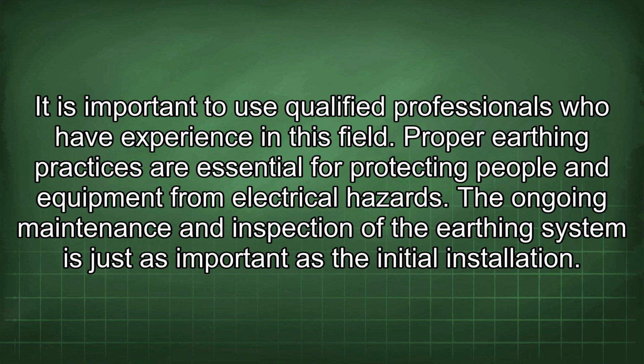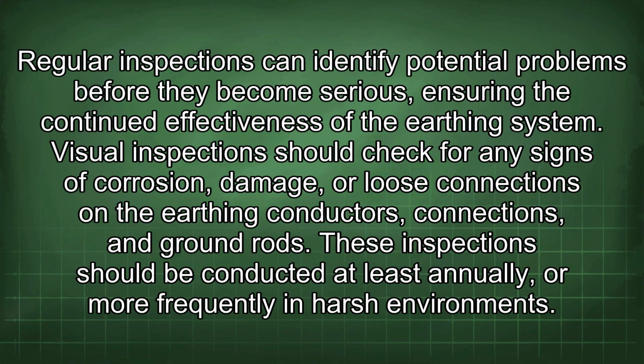The ongoing maintenance and inspection of the earthing system is just as important as the initial installation. Regular inspections can identify potential problems before they become serious, ensuring the continued effectiveness of the earthing system. Visual inspections should check for any signs of corrosion, damage, or loose connections on the earthing conductors, connections, and ground rods. These inspections should be conducted at least annually or more frequently in harsh environments.